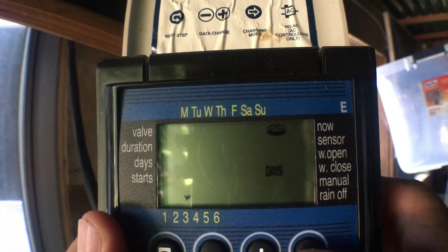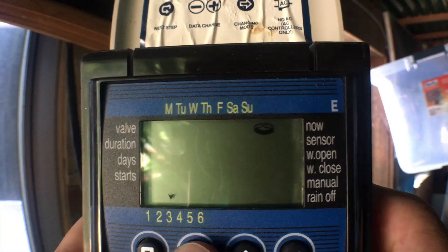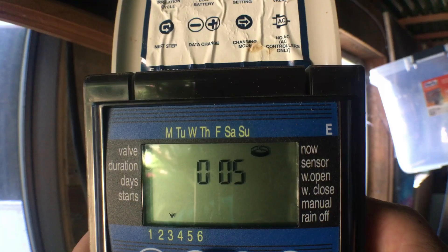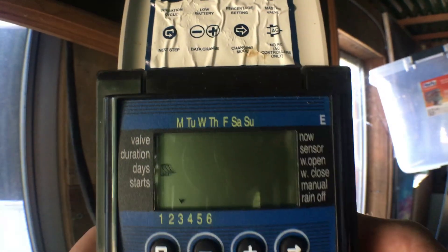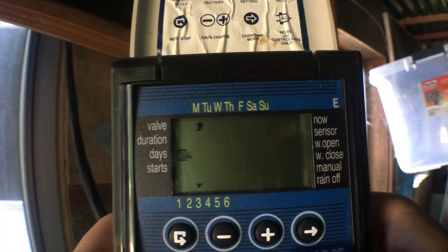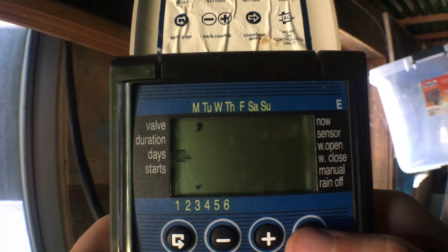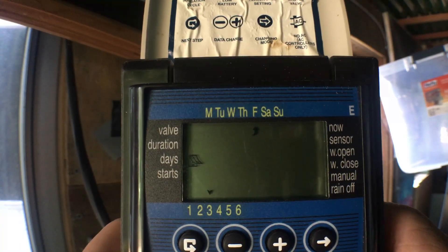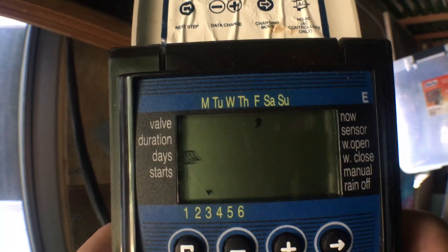Let's say we'll select Monday and Friday. I hit my arrow button — it starts blinking on the five days. We can take it back until we see the ONCE symbol come up, and then back down past hours and seconds. Once it's blinking on ONCE, I hit the arrow again and now we're in days-of-the-week mode. The days are blinking and I get to select which ones I want. I hit plus on Monday, then advance with the forward arrow to Friday and add that as well, then advance through the rest of the week. So we've got Monday and Friday selected.